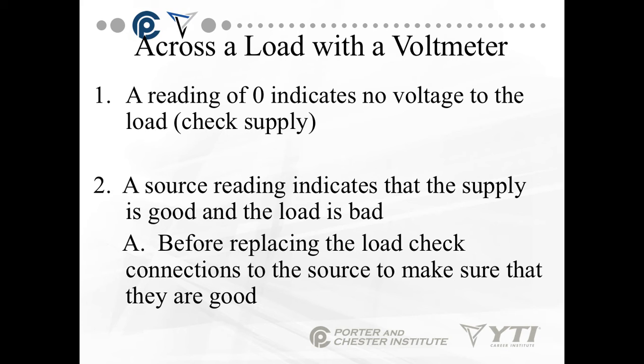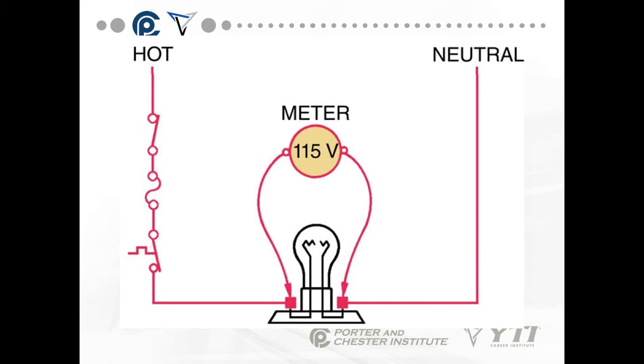Before replacing anything, always make sure to check the connections to the source and make sure the connections are good. If you read 115 volts across a light bulb and the light bulb isn't on, replace the light bulb. Same thing with a motor — if you read proper voltage across a motor and the motor isn't running, replace the motor. But always check and make sure the connections are good.